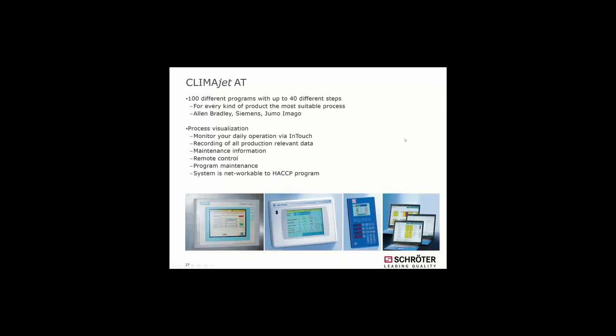In general on systems like this, we have a PLC which controls everything about the defrosting process. We use the surface temperature to monitor whether there is enough heat inside the room, or if we have to add some heat or some steam. Same for the humidity, which we measure, and therefore that is, I would say, the heart of the defrosting room.